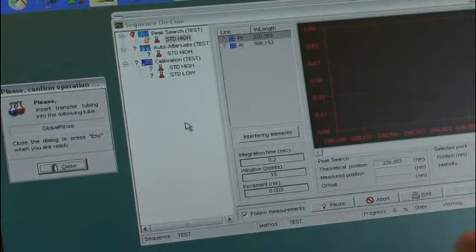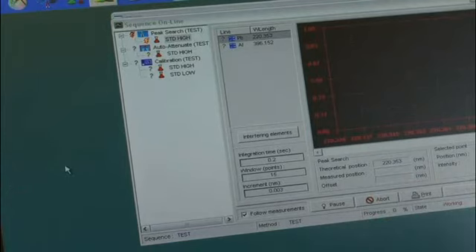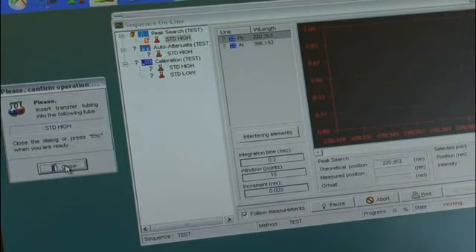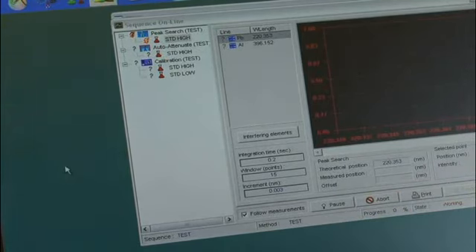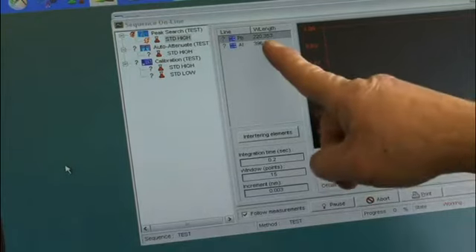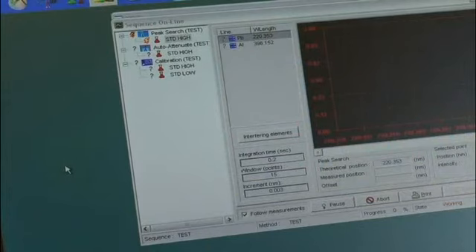Because I put a rinse time in, it's asking me to do the rinse, but I don't care about that. Now the first thing it'll do is look for the reference wavelength, which is that carbon line at 193. Well, first there's that 10-second transfer time, but normally I don't put one in because I do everything manually, and you know yourself when it's in the plasma. So right now it's looking for the reference. It's moving to that carbon line, and then it's going to start the acquisition. Once it finds the reference, then it'll go to the first wavelength in our sequence.